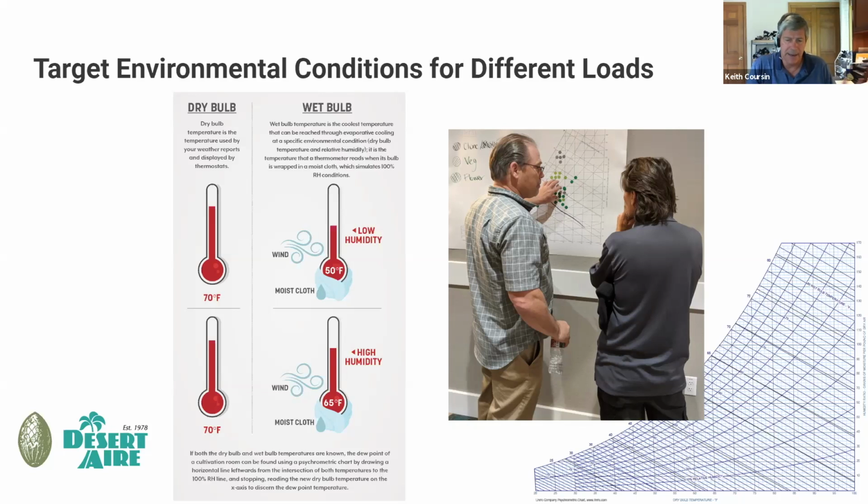and to the right is what we call the psychrometric chart, but that's just our way of plotting where everything goes. And I always hear the word relative humidity, and I just stress the term relative humidity is relative. It tells you nothing. Unless you know the corresponding dry bulb or corresponding wet bulb or corresponding dew point, you don't know what relative humidity means.